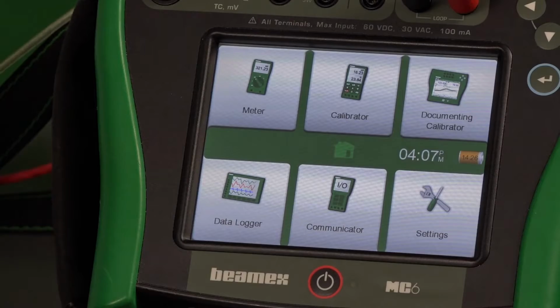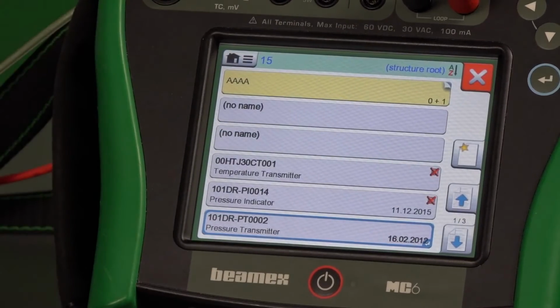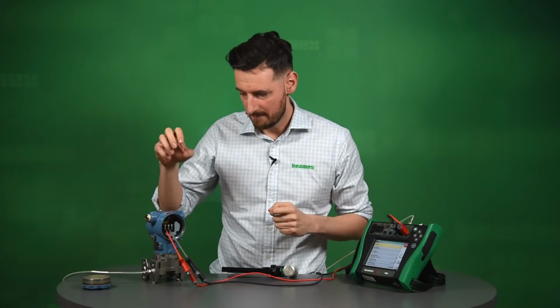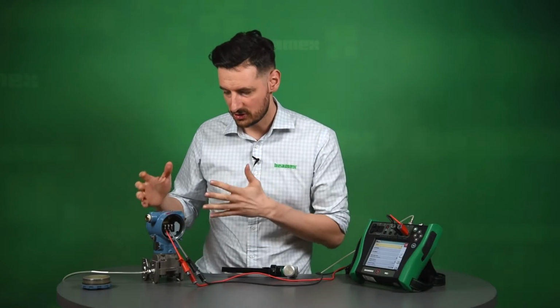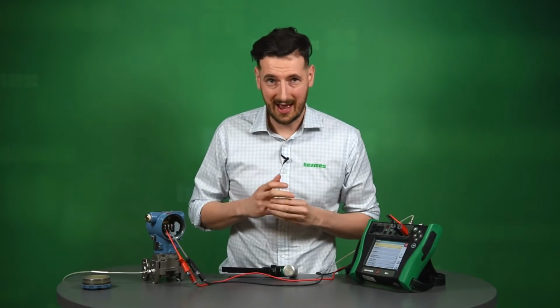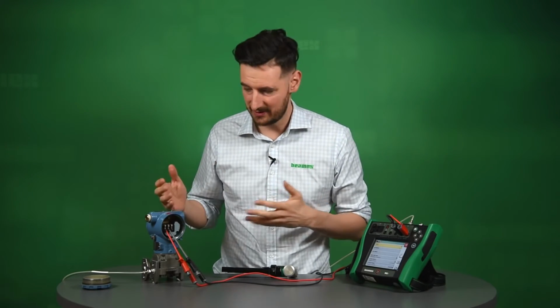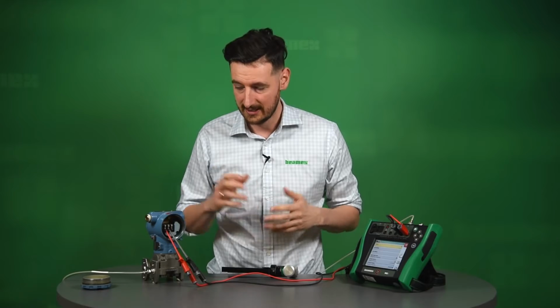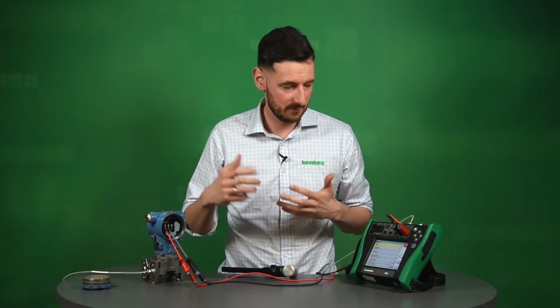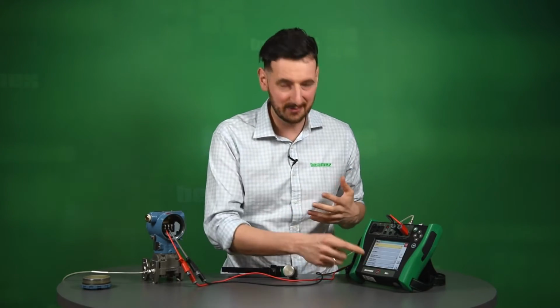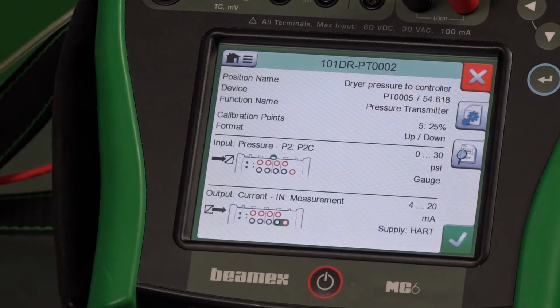So let's go to the documenting calibrator. The point of this is we're trying to establish how much this unit actually moved over time. It's been in service, it came back for recalibration right now. We need to check it against something, and we're checking that against a known standard, which is this calibrator. So that's the whole purpose. We could just check at random points, but of course this is not what we want to do. We want to do a proper documented calibration.